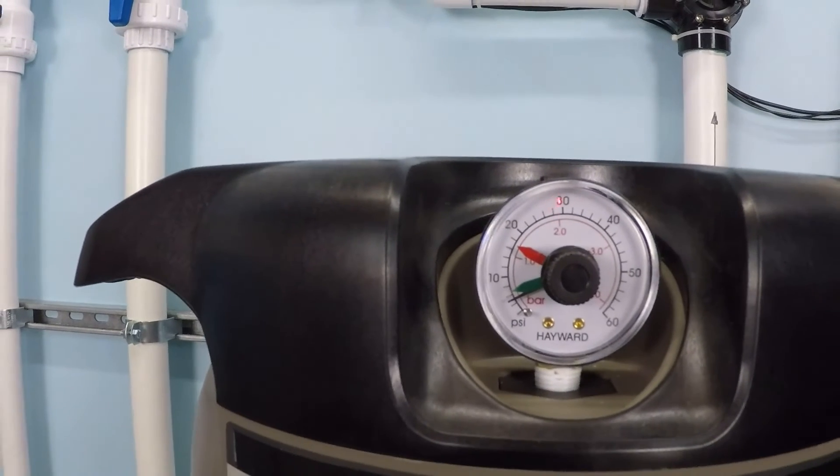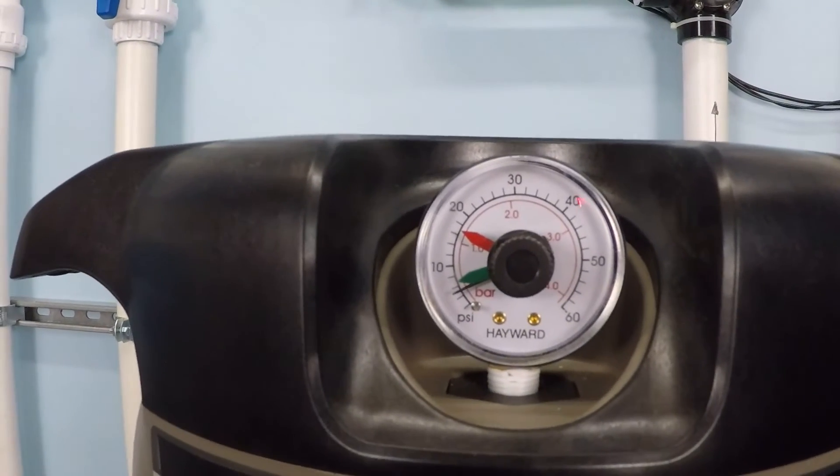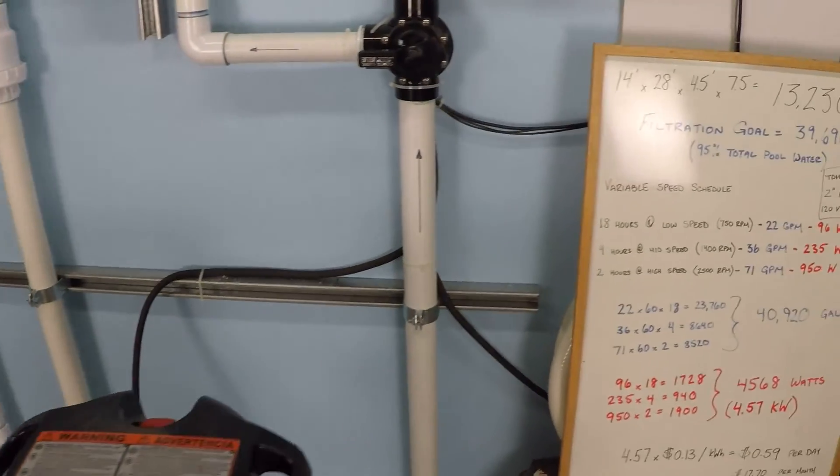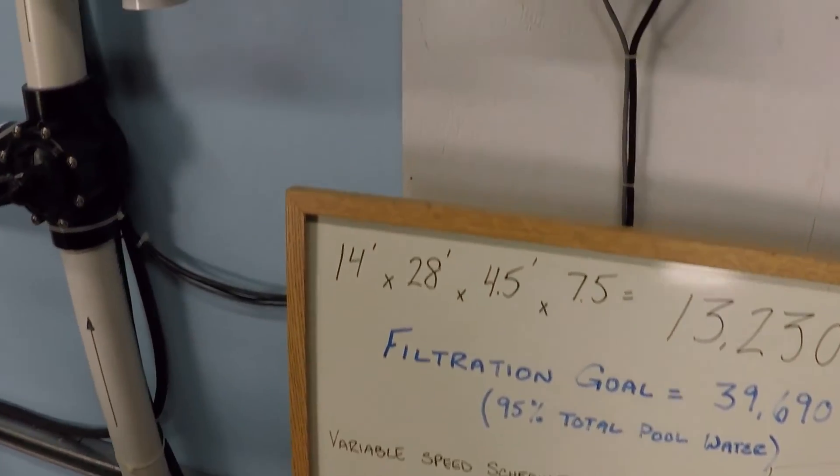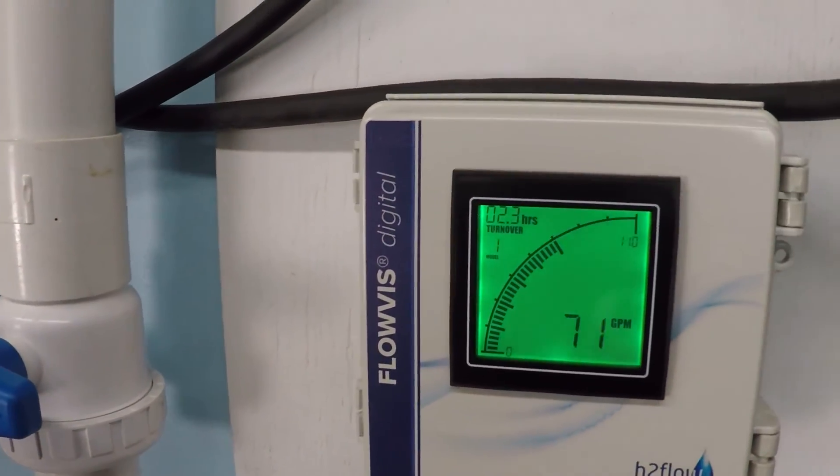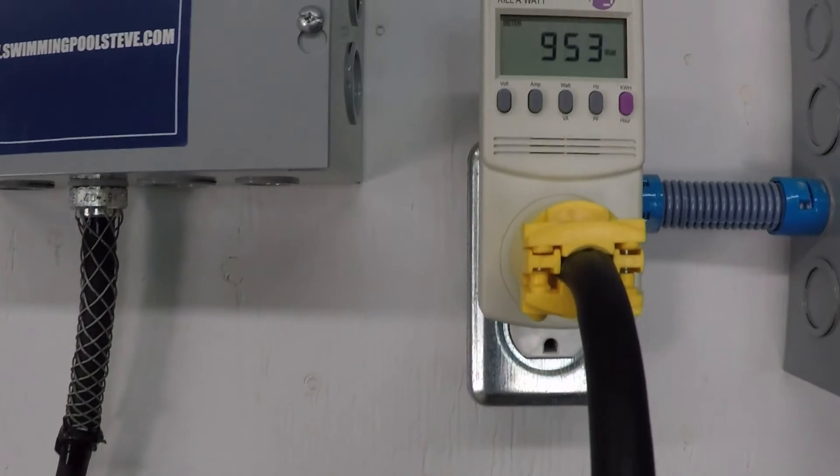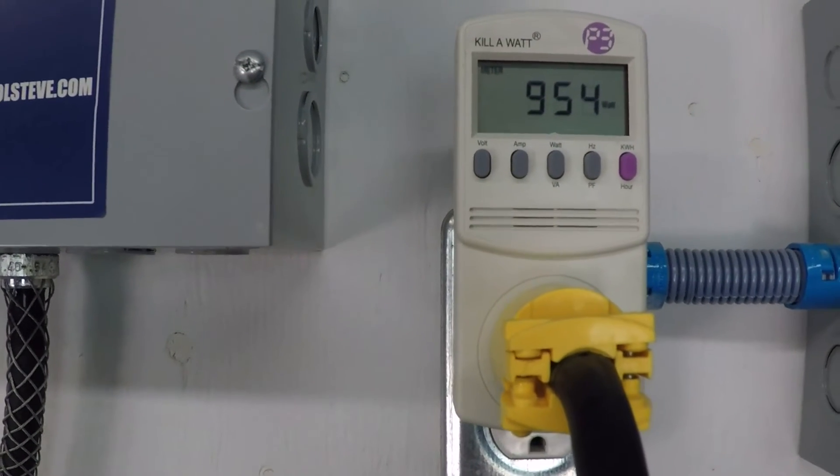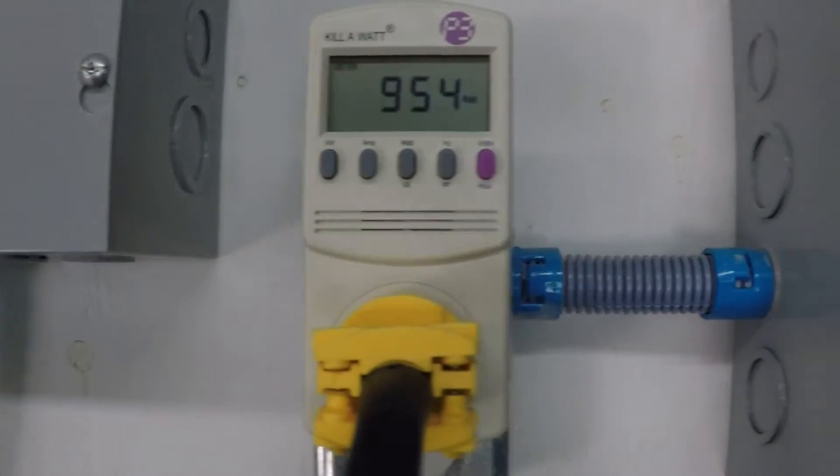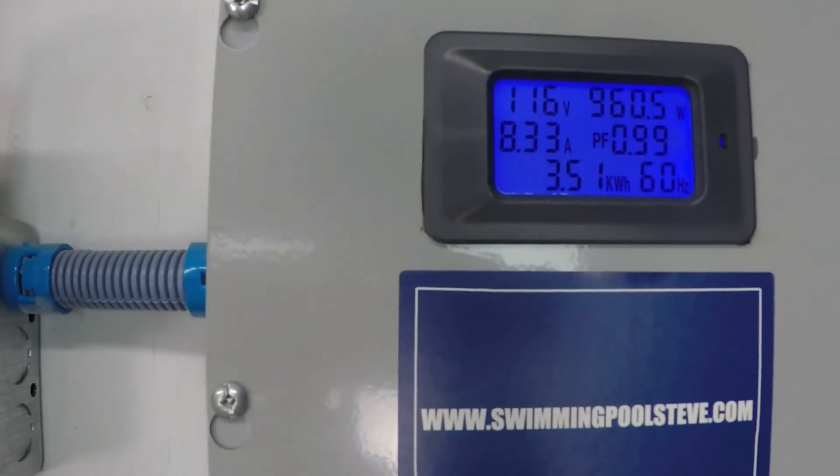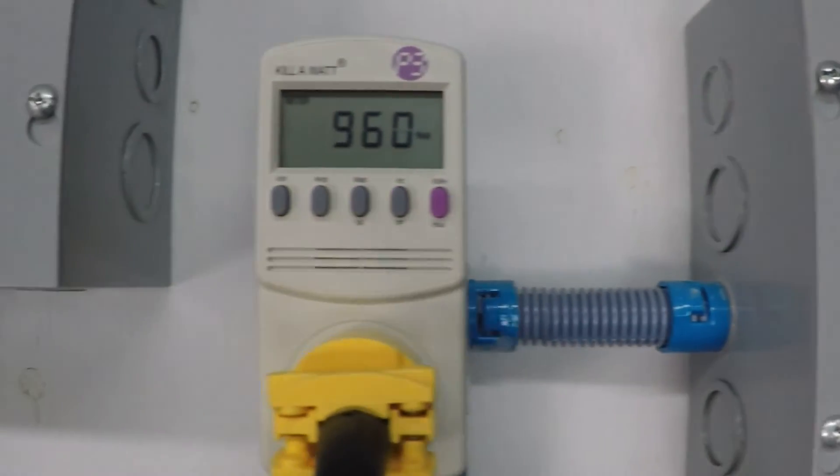We were barely 3 PSI on the gauge here. 71 gallons per minute. Under 1000 watts. Over 950 by a little bit. 960 here. But there is some variance in that 950 as you saw.